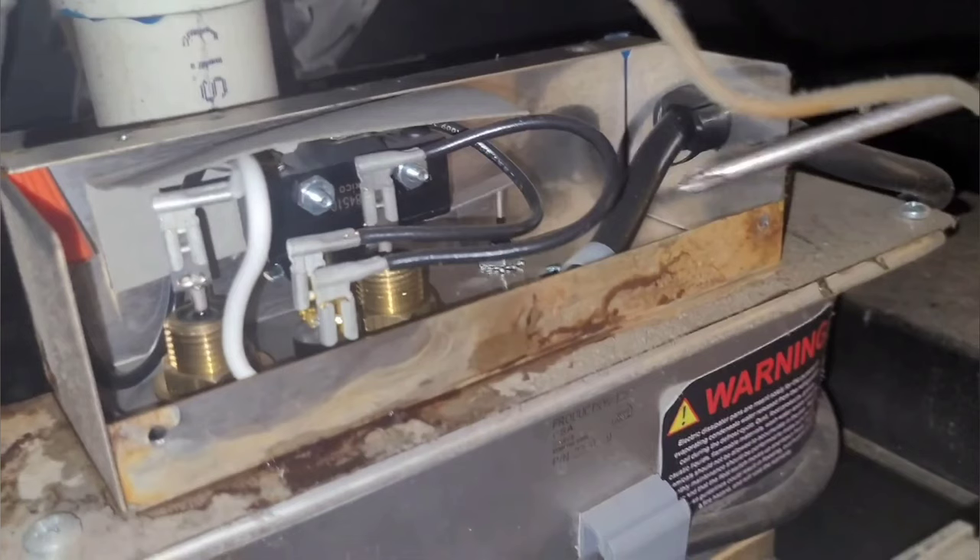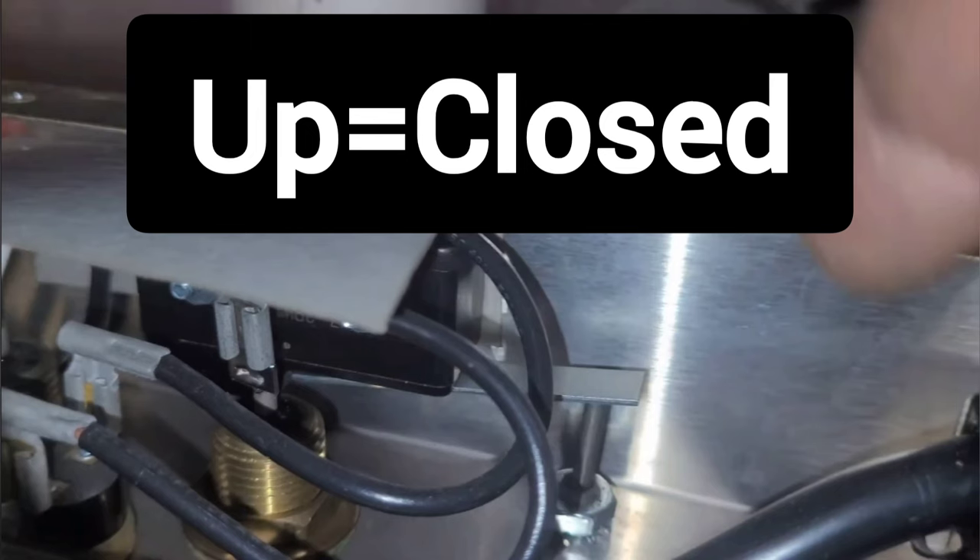We need to remove this electric cover and we'll find a little small switch in here. It's kind of hard to see, but it's back there. It's activated by a lever that's pushed up by a float that rests in the pan. When water starts rising in the pan, the float closes the switch, which should shut off your heating element.